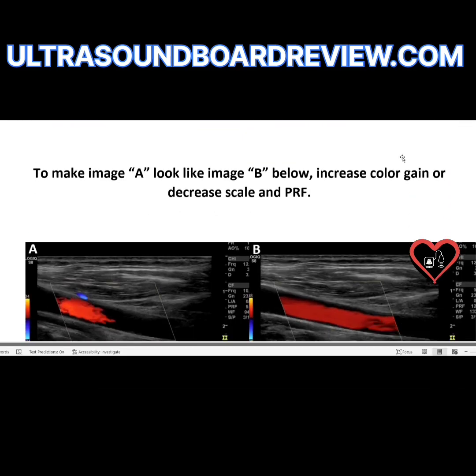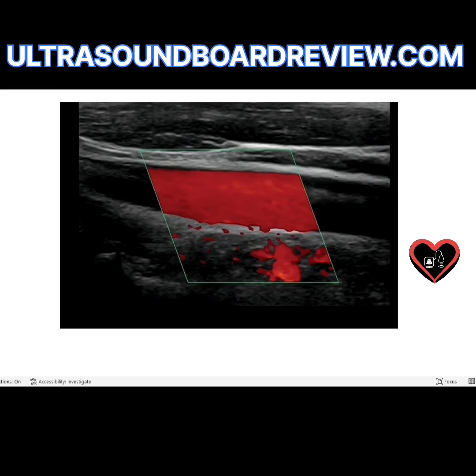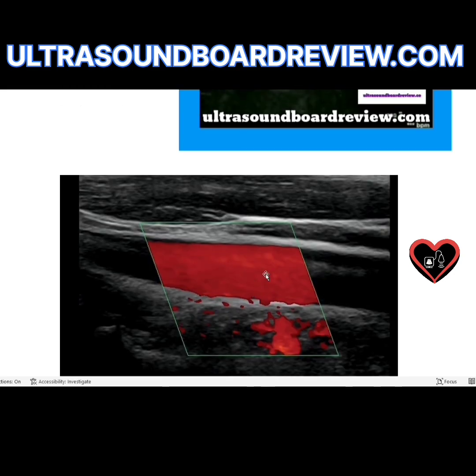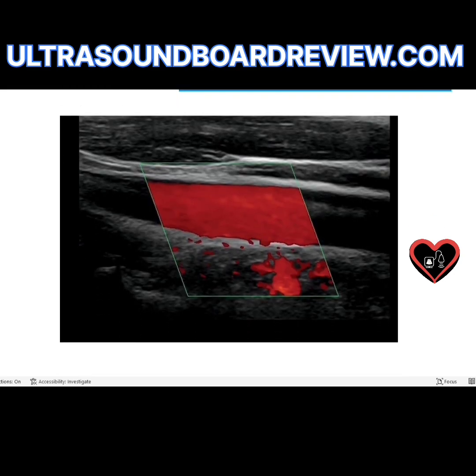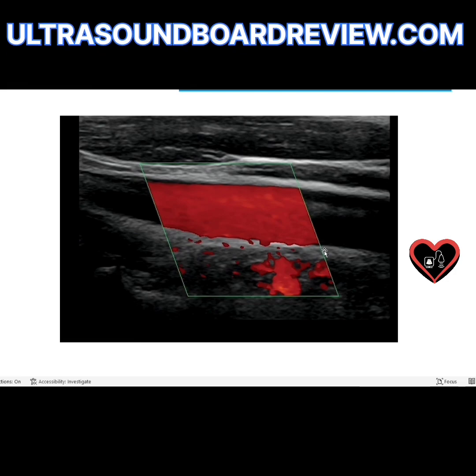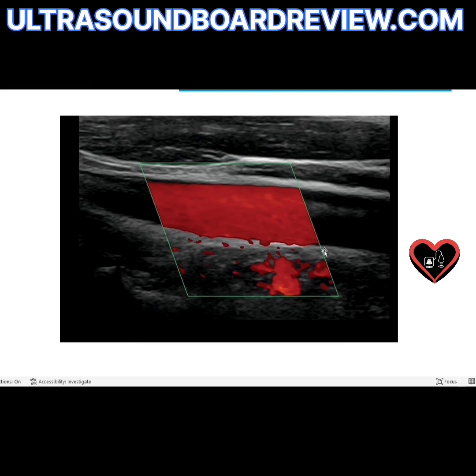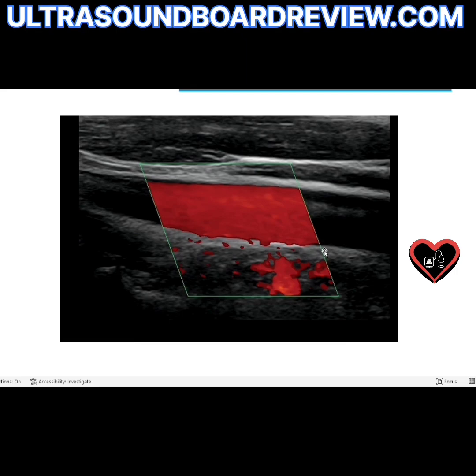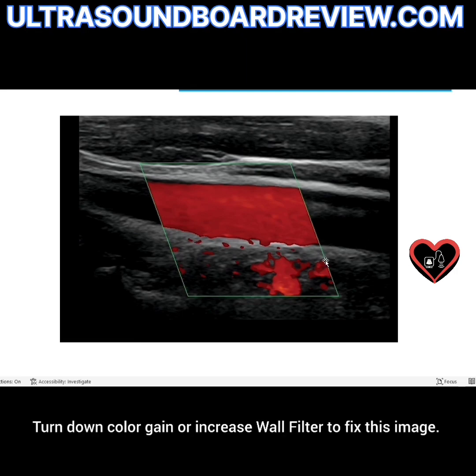Then they could ask: how would you fix a different image? Options: increase color gain, increase wall filter, increase frequency, or increase depth. Of those four options, you would choose increase wall filter, because increasing the wall filter eliminates these ghosting artifacts.